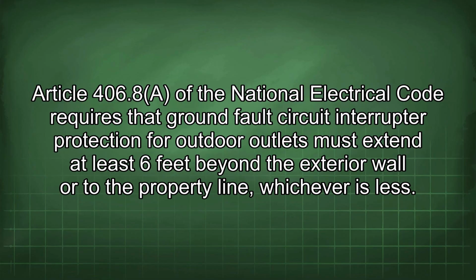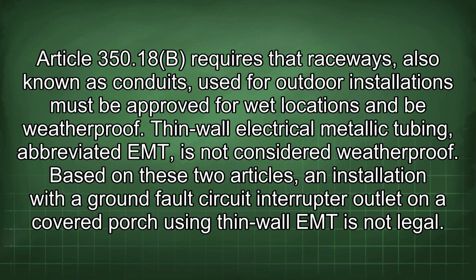Article 406.8 of the National Electrical Code requires that ground fault circuit interrupter protection for outdoor outlets must extend at least 6 feet beyond the exterior wall or to the property line, whichever is less. Article 350.18b requires that raceways, also known as conduits, used for outdoor installations must be approved for wet locations and be weatherproof. Thin wall electrical metallic tubing, abbreviated EMT, is not considered weatherproof.